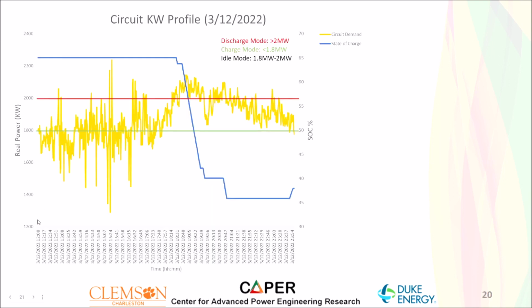So here's a visualization of exactly what's going on here. The yellow is going to be the circuit demand, the blue is going to be the state of charge, and the red and the green are the separations of the modes. So we can see here that we are in idle mode since it's flatlined all the way until we get about 10 minutes worth of data above 2 megawatts. And once we're above that 2 megawatts for 10 minutes, the algorithm decides to discharge that battery. And it'll discharge that battery all the way until around right here where it dips under, and we get a little flat line, but it comes right back up, so it discharges again.